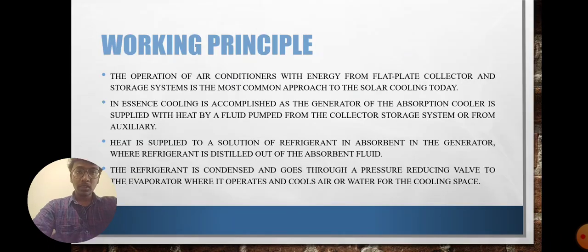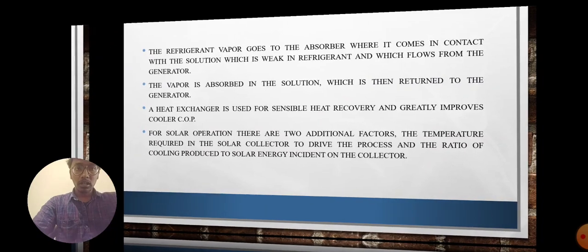And the next one is the working principle. How does it work? The operation of absorption air conditioners with energy from flat plate collectors and storage systems is the most common approach to solar cooling today. In essence, cooling is accomplished as the generator of the absorption cooler is supplied with the heat of a fluid pumped from the collection storage system or from auxiliary heat. Heat is supplied to a solution of refrigerant in absorbent in the generator, where refrigerant is distilled out of the absorbent fluid. The refrigerant is condensed and goes through a pressure reducing valve to the evaporator, where it evaporates and cools the water for the cooling space. This is the working principle of solar cooling.